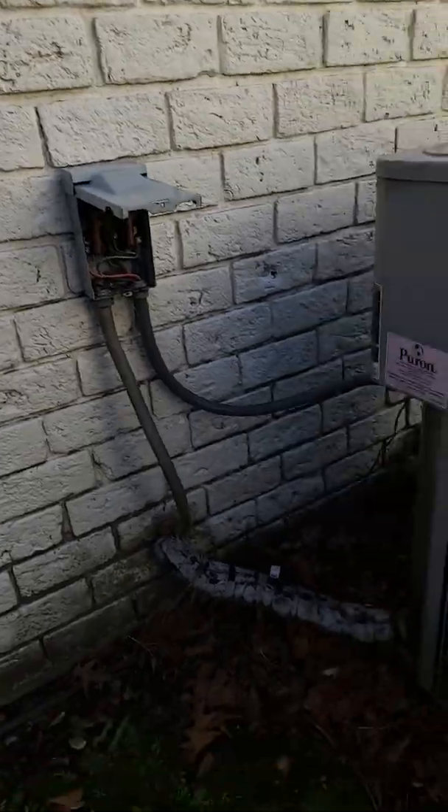It's whatever the wires in the copper pipe can handle as far as amperage rating in a short circuit, in which case you can start a fire. So I'm going to mark that one as deficient. Thought I'd share — everybody have a great day.